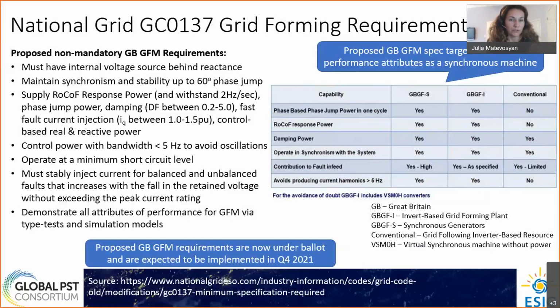Then there is a requirement to withstand 2 Hz per second rate of change of frequency, a requirement for phase jump power that needs to be provided, damping, fast fault current injection, and control-based real and reactive power injection. Control power should be provided with bandwidth less than 5 Hz to avoid oscillations. There will be a minimum short circuit level at which the device is expected to operate, and that will be bilateral because it will depend on location for the service. It must inject current for balanced and unbalanced faults, and current should increase with fall in retained voltage without exceeding peak current rating. So this is also important.